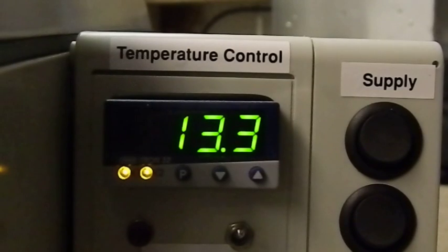What we would then do is run the machine up by changing the set point and taking the set point up to 37.5. Allow the machine to come up to that temperature, and then repeat the procedure, going through to offset, putting in whatever variation there is. In normal circumstances, that variation will be no more than 0.1 of a degree. It's just a nice way of us being able to set them up virtually cold when they first go on test, and not having to worry about them until they hit the operating temperature of 37.5.